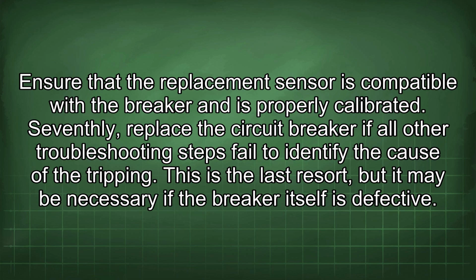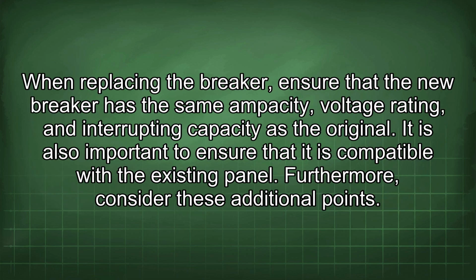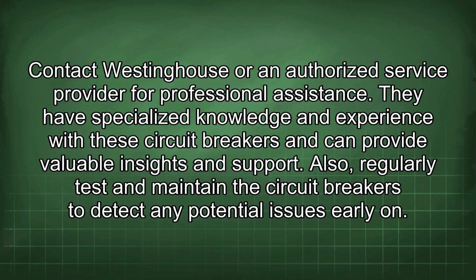Seventhly, replace the circuit breaker if all other troubleshooting steps fail to identify the cause of the tripping. This is the last resort, but it may be necessary if the breaker itself is defective. When replacing the breaker, ensure that the new breaker has the same ampacity, voltage rating, and interrupting capacity as the original. It is also important to ensure that it is compatible with the existing panel. Furthermore, consider these additional points. Contact Westinghouse or an authorized service provider for professional assistance. They have specialized knowledge and experience with these circuit breakers and can provide valuable insights and support.